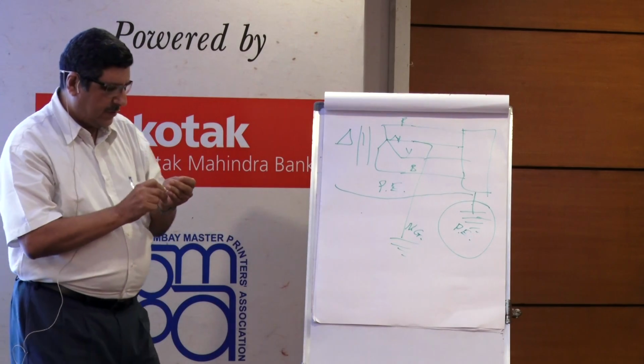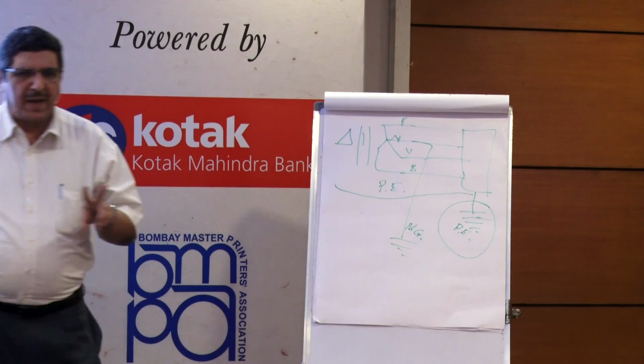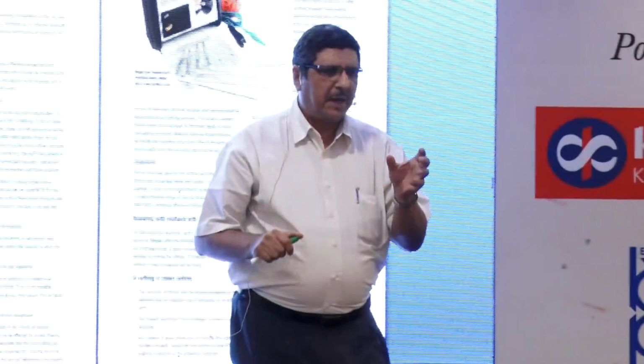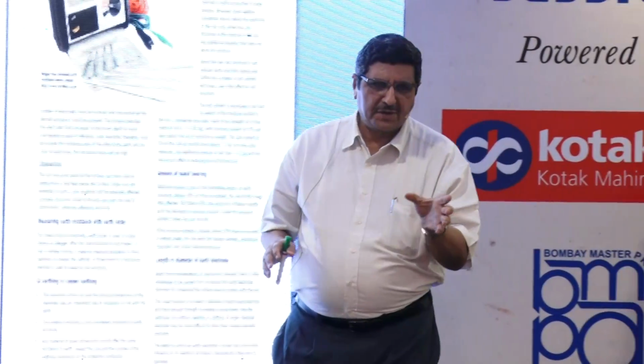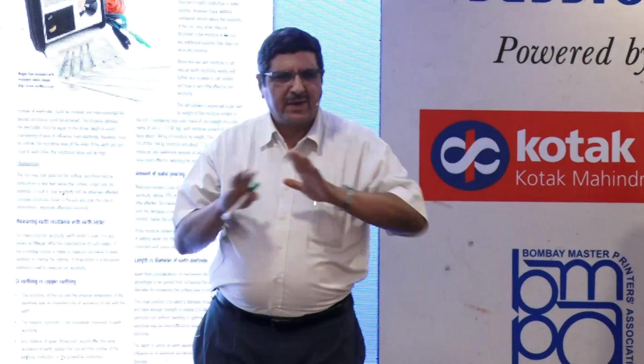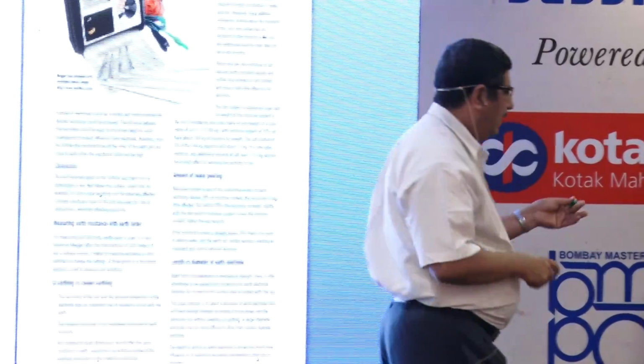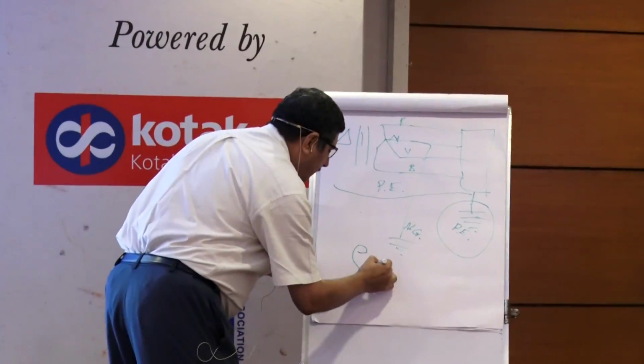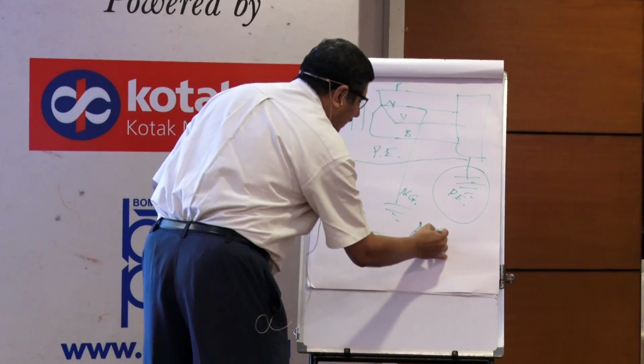Now, as per the earthing schedule, there are two options: pipe and plate. One pipe you have to take of 38 mm, that is 1.5 inch. I suggest 3 inches, very simply, because there is a formula as per IS which defines rho. Now, this takes area into consideration.